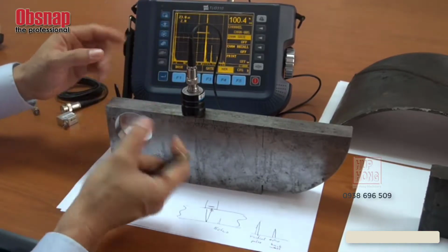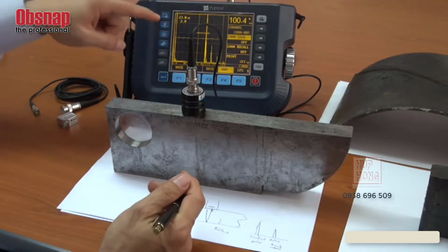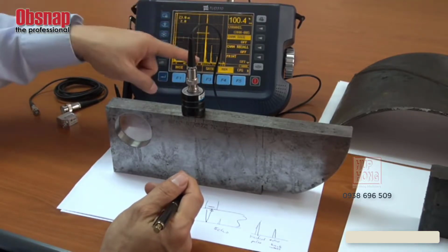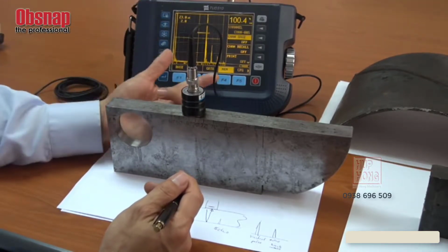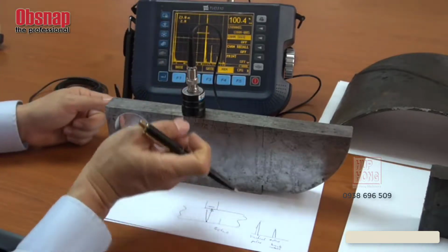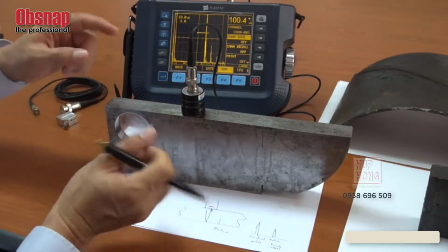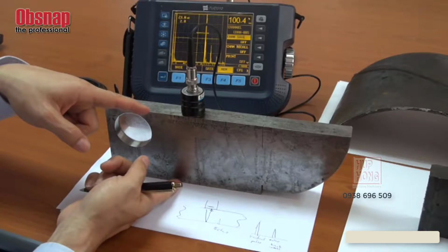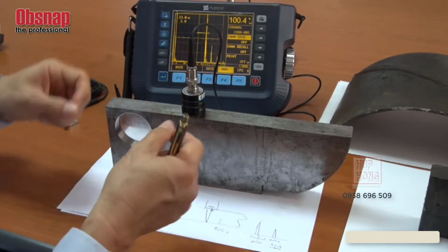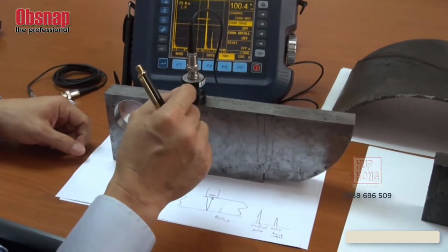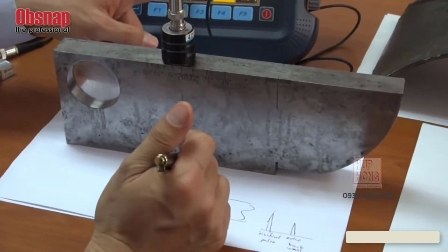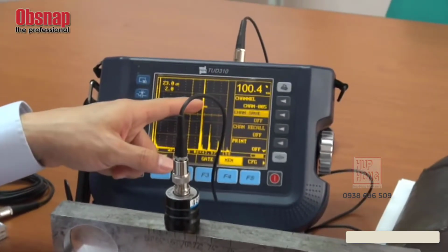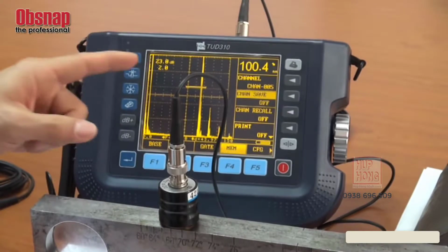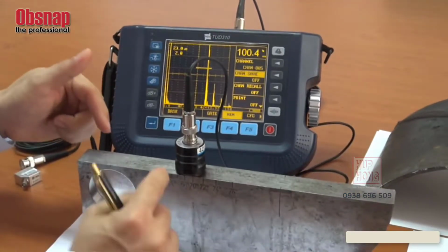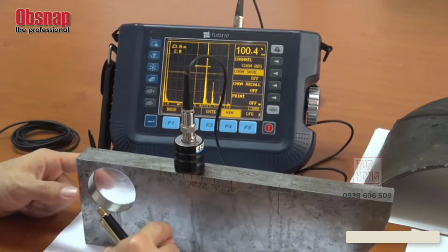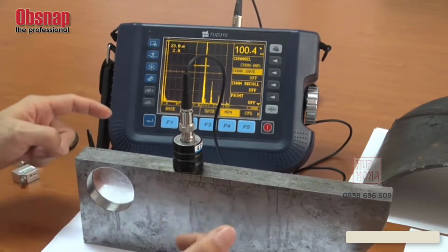Because we do the calibration in such a way that we tell this unit that the pulse you obtain is at a distance of 100 mm. Meaning, why 100 mm? Because our standard block is 100 mm thick. So in future, when we are doing the measurement or detection, right? The moment we see this pulse and then we use this gate to measure, then we know that the reading is accurate. Why is it accurate? Because we calibrated this meter according to a standard. Okay, right?